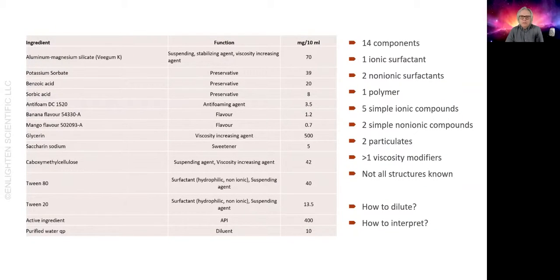To measure the zeta potential for something like this by electrophoretic light scattering is a big challenge. It has to be diluted, and there's the clay - it's a lot bigger than the drug and has a higher refractive index, so it may dominate the scattered light signal. You may not see a difference in the zeta potential even though the drug particles may be demonstrating some different surface chemistry that would lead to a different zeta potential. It could explain why you're having a problem, but you won't see it because it's swamped by the other particulate material in your product.